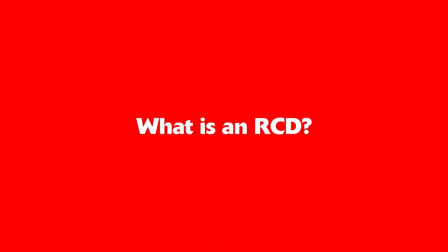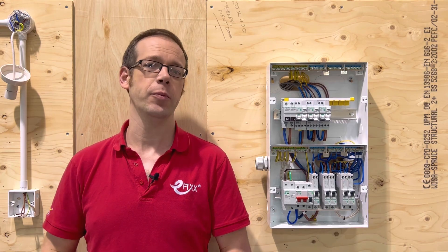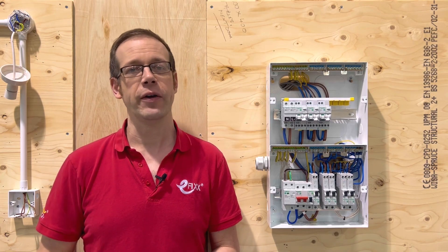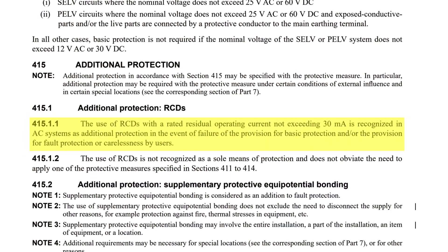So what is an RCD and what kind of protection does it offer? Well an RCD offers two main forms of protection. The one that's probably the most common nowadays is found in regulation 415.1.1. The use of RCDs with a rated residual operating current not exceeding 30 milliamps is recognized in AC systems as additional protection in the event of failure of the provision for basic protection and or the provision for fault protection or carelessness by users.